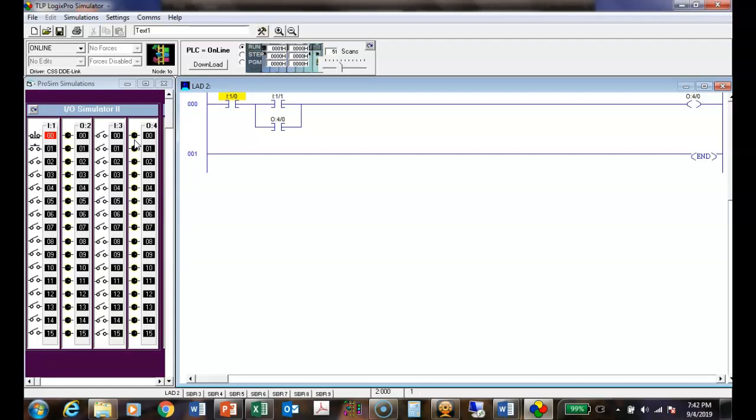It'd be a real small motor. PLCs cannot run big loads. It can run a coil. So I could run that big relay over there, right? You see that? It could bring in that coil and that relay down at the bottom, and then I could turn on that motor down there with it. The PLC can't do it. An indicator light, like a green light? Well, that's up to you. All I'm saying is I don't have to wire a light to this output.